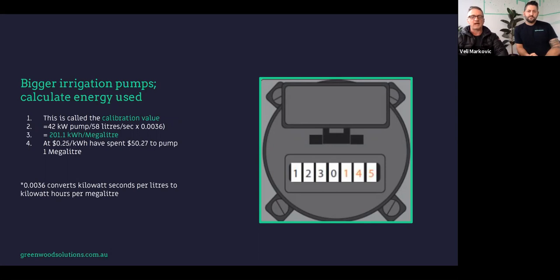We use something called the calibration value. For those who know their pumps, this is second nature; for those who don't, hopefully we're teaching something new. The calculation is 42 kilowatts over 58 litres per second, times 0.0036. Lots of numbers, but at the end of the day, this is a mathematical calculation to find out how much that pump is actually using, energy-wise and cost-wise, to pump 1 megalitre.